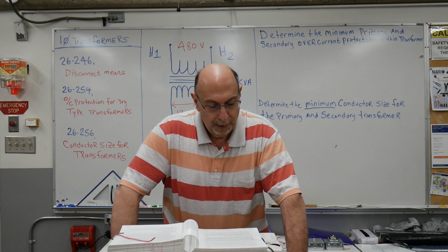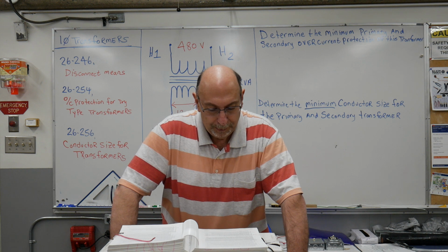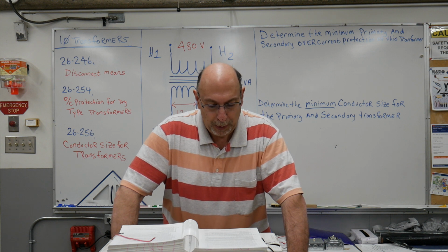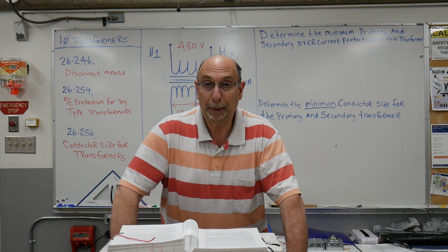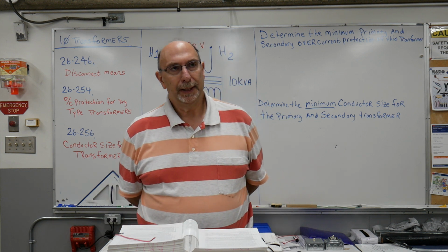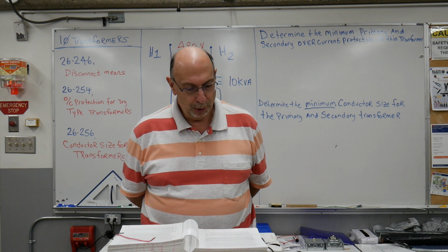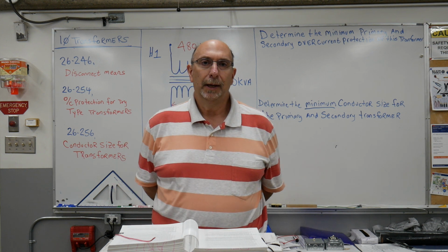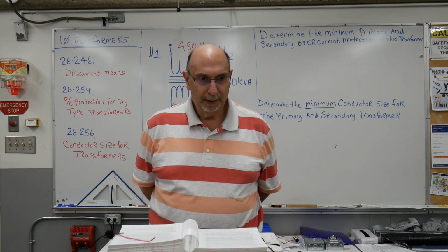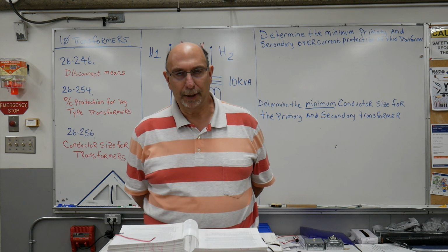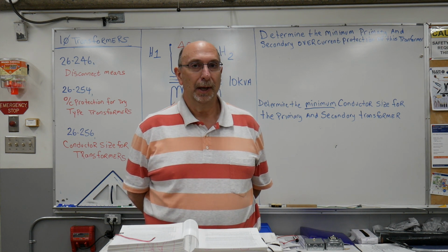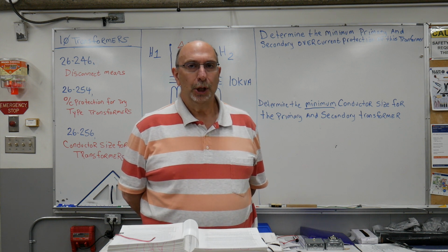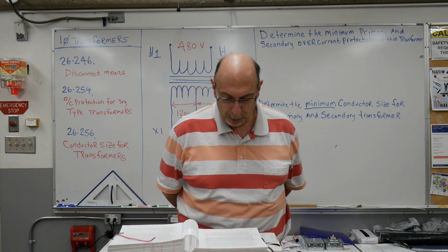Sub-rule 2. I'll let you read that on your own. But sub-rule 3 states, where a value not exceeding 125% of the rated primary current of the transformer as specified in sub-rule 1 does not correspond to the standard rating of the overcurrent device, the next higher standard rating shall be permitted. So for example, let's say you do a load calculation on a transformer and you add in the 125% for the transformer overcurrent device, then you could go up to the next standard size. So if you come to, let's say, 16 amps for your FLA, full load current, you could then bump up to 20 amps. That is what that rule is stating.